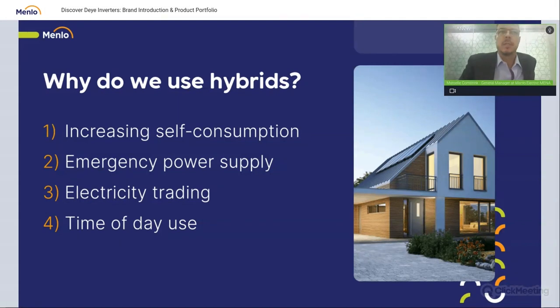Why do we use hybrids? Hybrids are basically to increase self-consumption, provide emergency power supply, electricity trading, and time of day use. Time of day use works in certain areas where you have a high tariff with your local energy provider; in some countries it makes more sense to charge the battery on the low tariff and then discharge it during the high tariff. This is commonly used in countries like South Africa, where during peak hours tariffs are 5-6 times higher than the standard low tariff. People realize that installing battery solutions and using the battery during that peak time costs them less money.